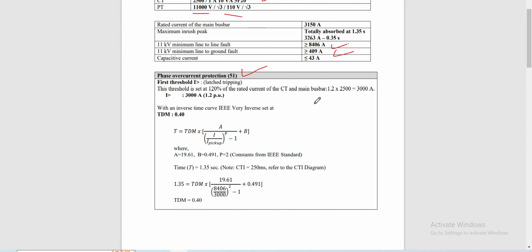So let's start on relay 51. This relay 51, by the way, is for the first threshold. For our first threshold, this is set at 120% of the rated current of the CT. Our CT is rated as 2,500 multiplied by 120%. So our first threshold current pickup setting is set at 3,000 ampere or 1.2 per unit. We'll just multiply 3,000 by the relay ratio of 1/2,500.